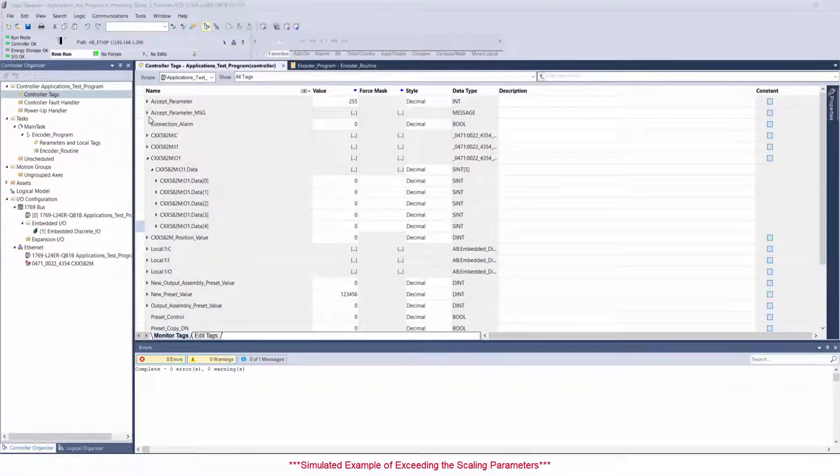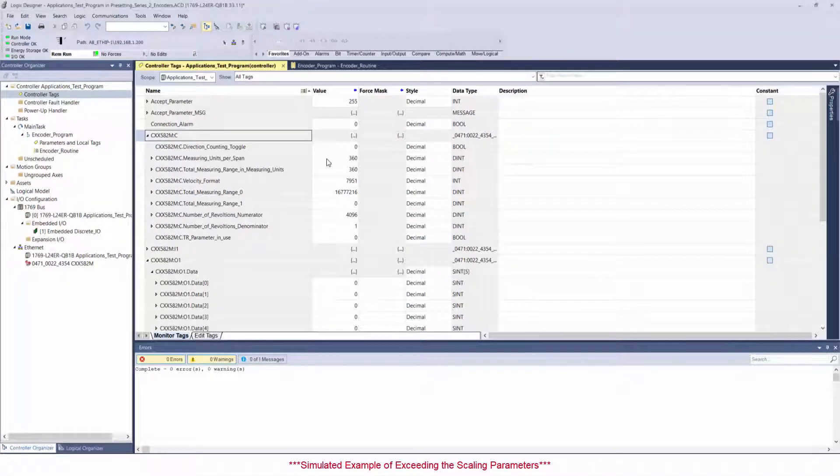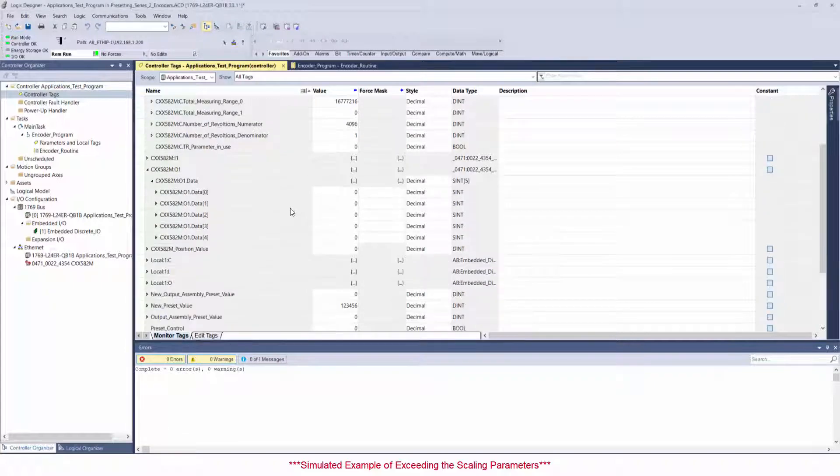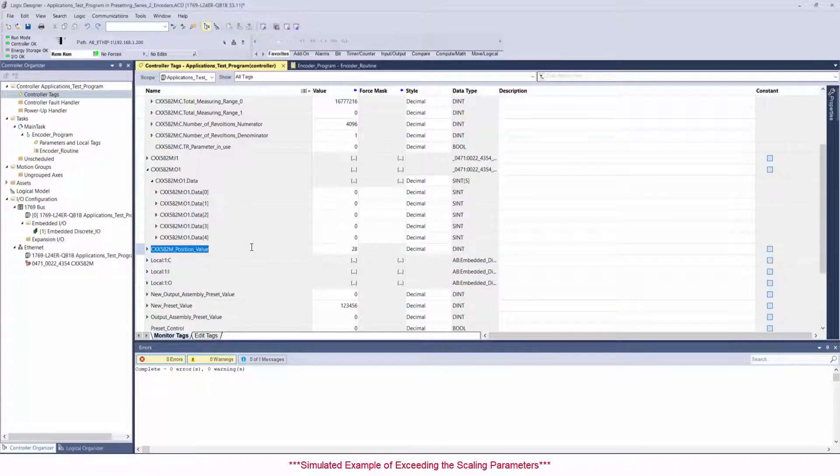Now try with your own value, keeping in mind that it must be a value within the measuring range of your device's scaling parameters. For example, if you've programmed your encoder to count between 0 and 359, you cannot ask it to output a value exceeding 359.